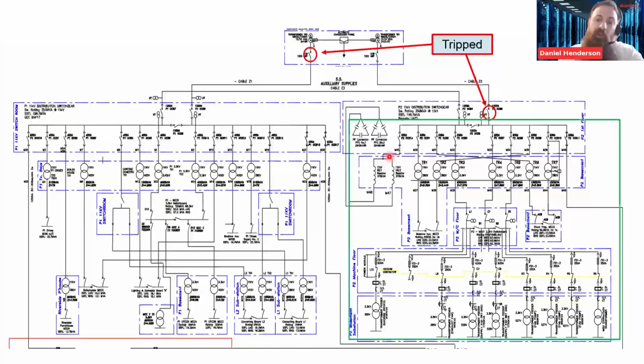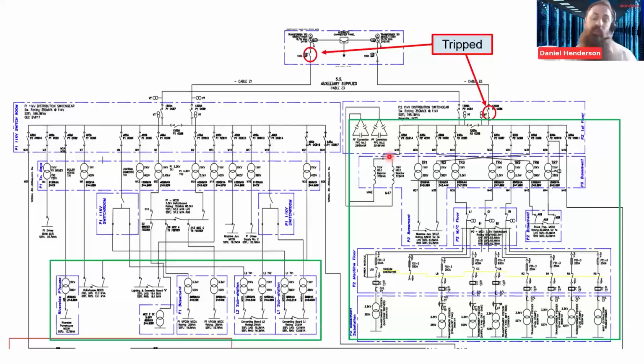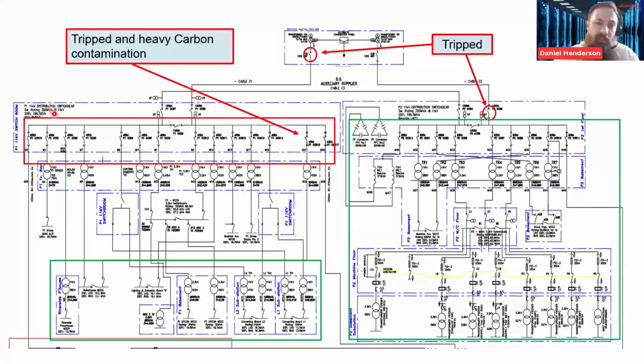And then I've walked the whole network. So this is cables, transformers, LV circuit breakers, the downstream 6.6 and 3.3 kV switchgear and transformers, and there's no signs of any damage. So I'm fairly confident that that's all okay. I then walked to the other side of the site. It's quite a large site. It's a couple of kilometers long. And then all these transformers and LV switchboard, there's no damage, there's no signs of any flags on the relays or anything like that.